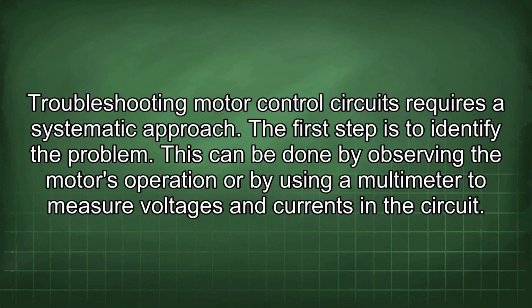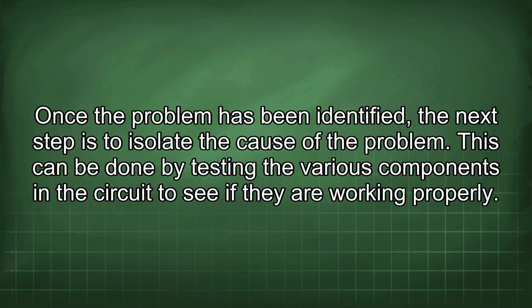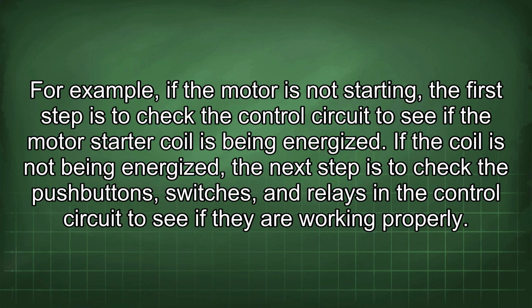Troubleshooting motor control circuits requires a systematic approach. The first step is to identify the problem. This can be done by observing the motor's operation or by using a multimeter to measure voltages and currents in the circuit. Once the problem has been identified, the next step is to isolate the cause of the problem. This can be done by testing the various components in the circuit to see if they are working properly. For example, if the motor is not starting, the first step is to check the control circuit to see if the motor starter coil is being energized. If the coil is not being energized, the next step is to check the push buttons, switches, and relays in the control circuit to see if they are working properly.